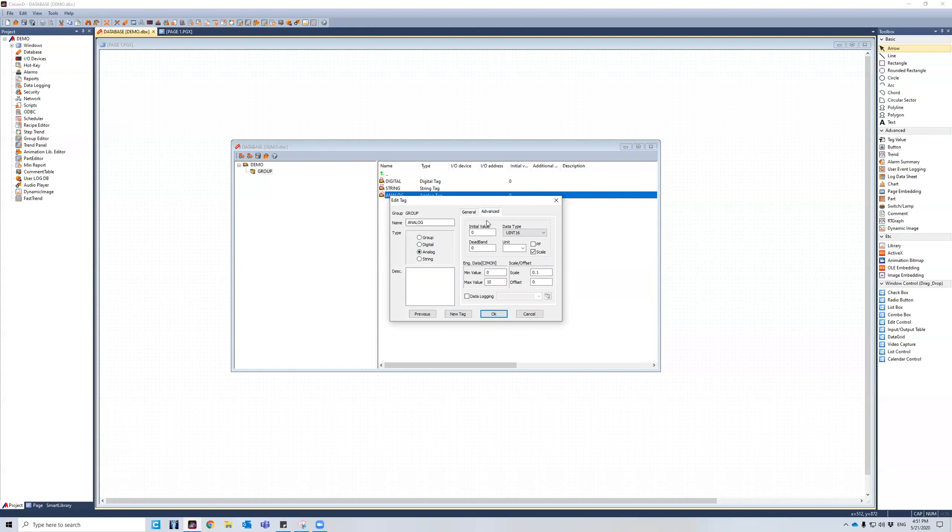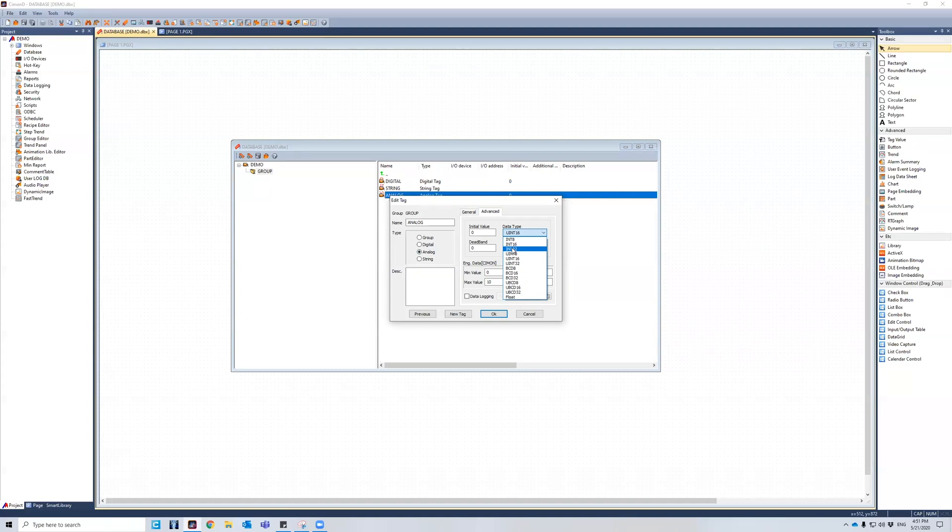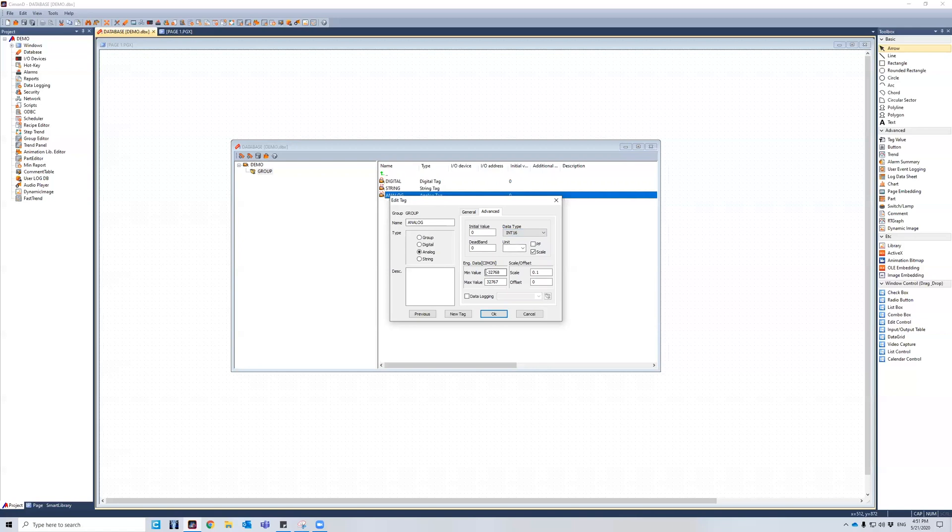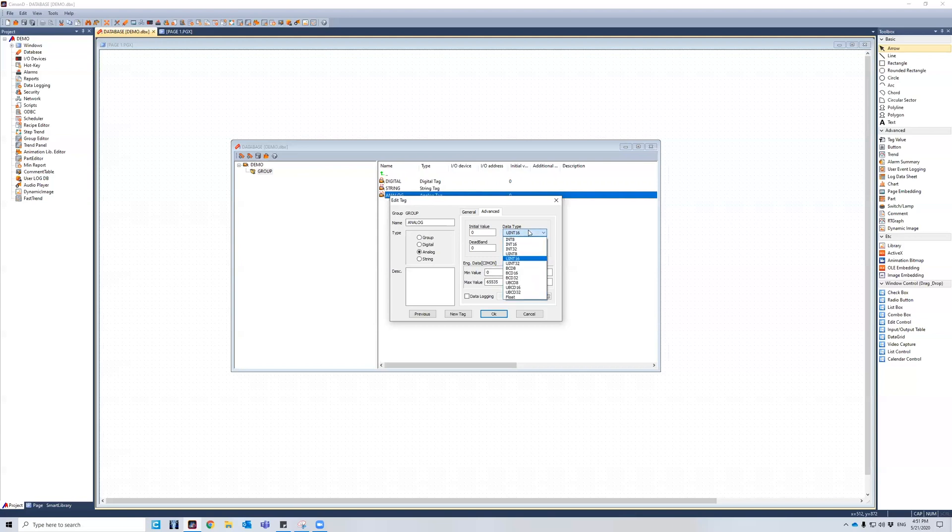Now, a little bit about the advanced parameters. I can create an initial value for an analog. I can make it whatever I want. I can change the data type from signed integer. So this is where I would get a negative value. So if I pick integer 16, I get a negative right here. And if I do unsigned 16, I get rid of that negative and I get only positive numbers. I can also choose binary coded decimal. And I can also choose float data if you're working with decimals themselves.